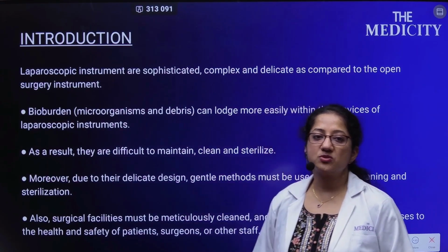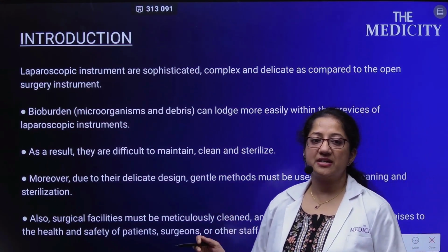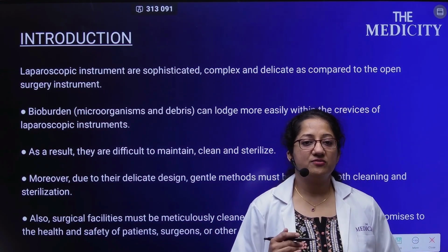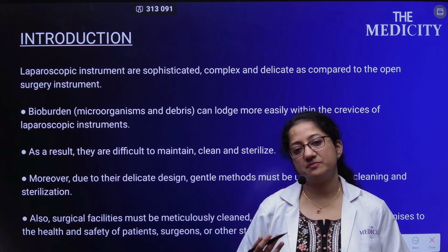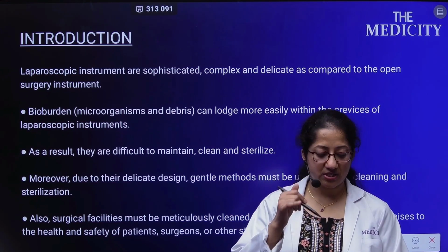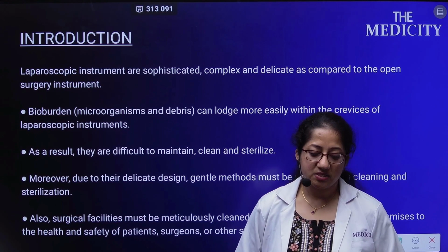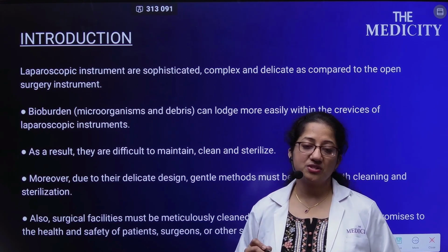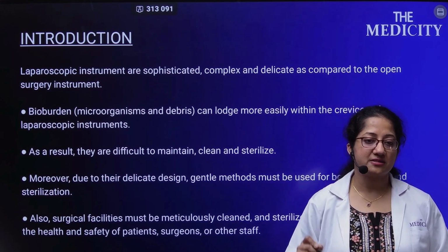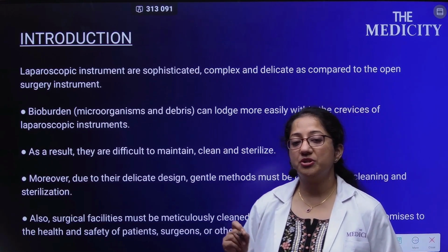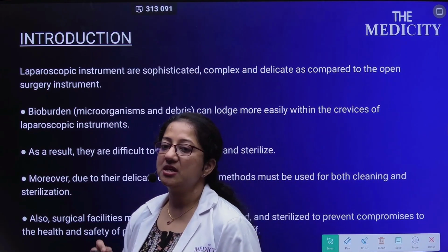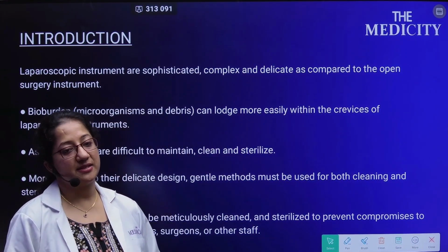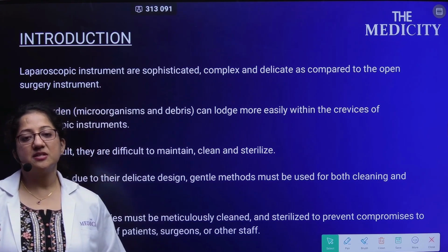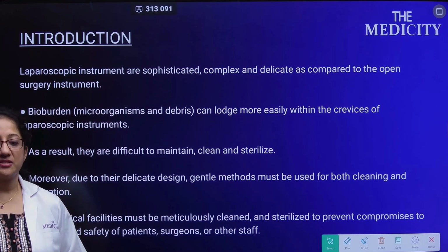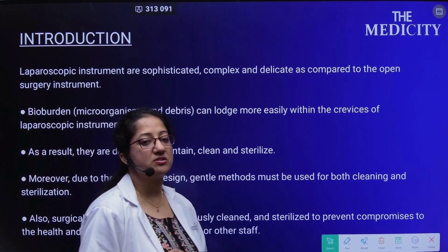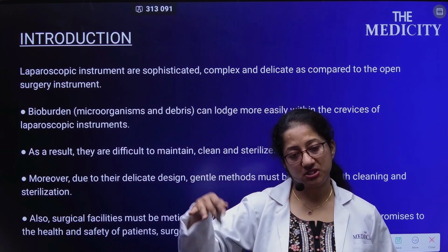The laparoscopic instruments are sophisticated, complex, delicate instruments. They have bioburden, that is microorganisms and debris, which can lodge into the crevices, especially if there's any break in it. As a result, they can be difficult to maintain, clean and sterilize. Moreover, due to their delicate design, gentle methods must be used for both cleaning and sterilization. Surgical facilities must be meticulously cleaned and sterilized to prevent compromising the health and safety of the patients who are further using it.